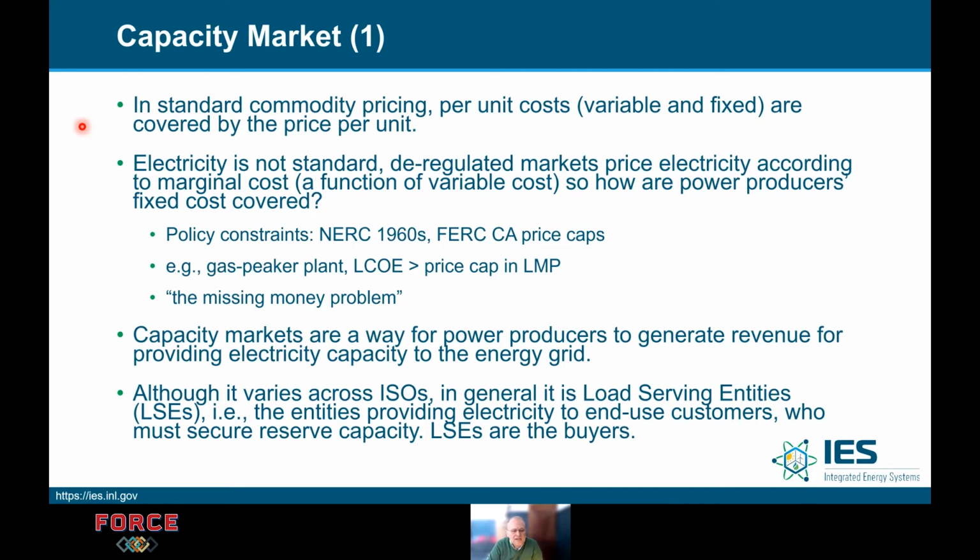Okay, so how the capacity market works is, again, generators are bidding into a market, but now they're bidding to provide services for 3 months out, or to provide services for 3 years out, to have capacity online and available. And so that's a method of stability that the grid operator can use to make sure that they have capacity to operate their system X amount of time out from now.